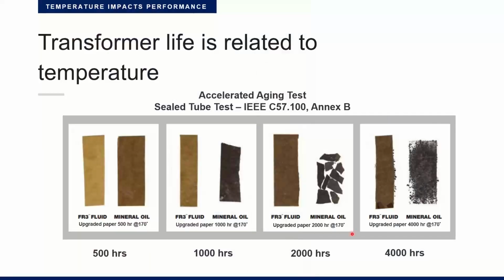Thanks a lot, Stefan. So the life of a transformer is related to the life of the insulation material. And life of insulation material is directly related to temperature. And which insulation material do we have in a transformer? So we have, in general, paper and oil. We should look at the paper more carefully. Why? Because you can change the oil during the lifetime of the transformer several times, but you cannot change the paper. This means if your transformer is 40, 50 years old, the paper inside the transformer is also 40, 50 years old.